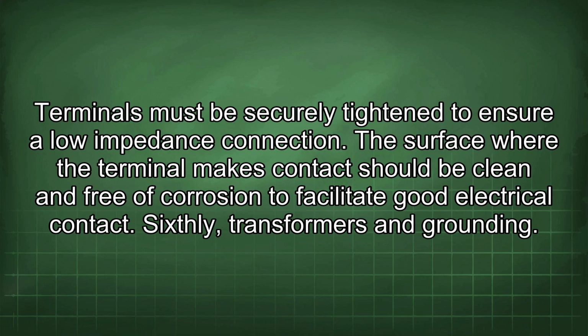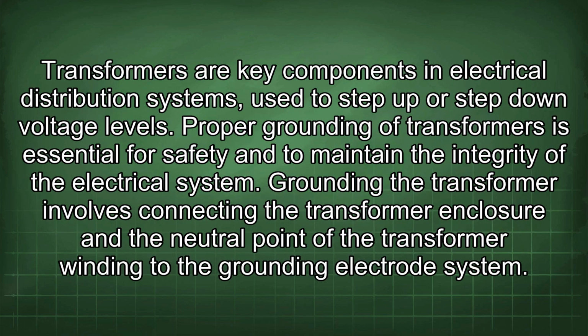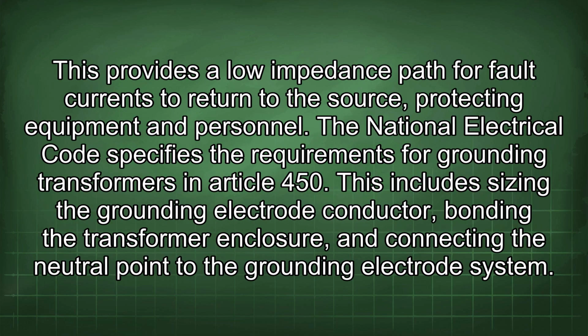Sixthly, transformers and grounding. Transformers are key components in electrical distribution systems, used to step up or step down voltage levels. Proper grounding of transformers is essential for safety and to maintain the integrity of the electrical system. Grounding the transformer involves connecting the transformer enclosure and the neutral point of the transformer winding to the grounding electrode system. This provides a low impedance path for fault currents to return to the source, protecting equipment and personnel.